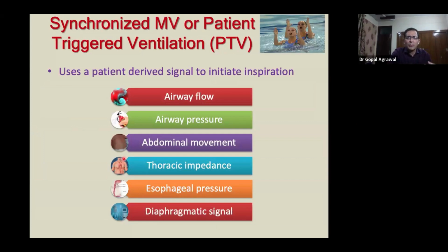This is what is called patient-triggered ventilation, where the patient will trigger the ventilation and the machine will try to synchronize each and every breath. So how does the machine synchronize? There are various trigger mechanisms. I've given a list of all these. The basic is flow trigger, which is commonly used in neonates. The others are pressure trigger, which is not commonly used; I've avoided it nowadays. Other less commonly used ones are abdominal movement signals, thoracic impedance, esophageal pressure, and something called the diaphragmatic signal in NAVA, which we'll be discussing later in the slides.